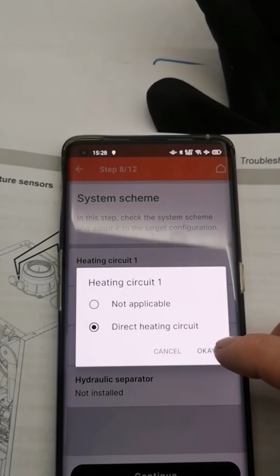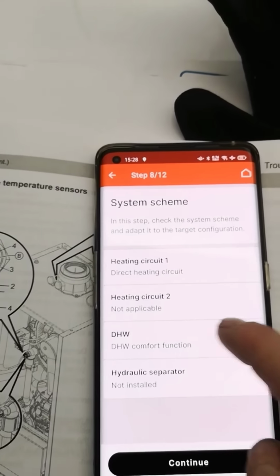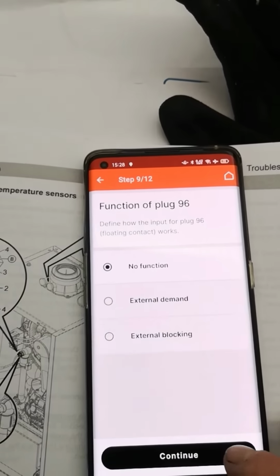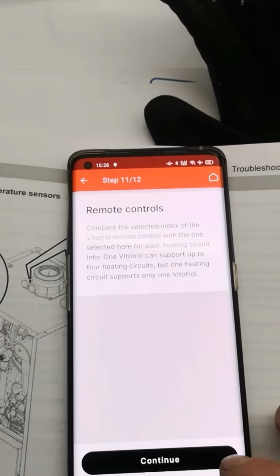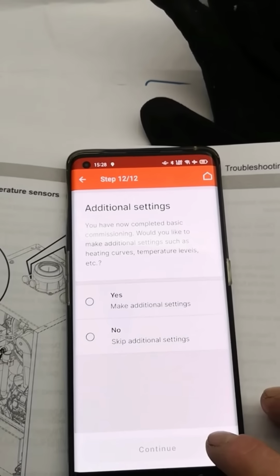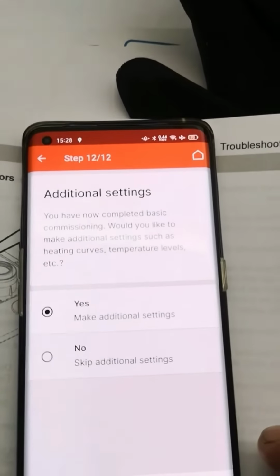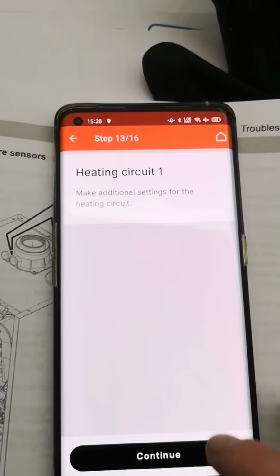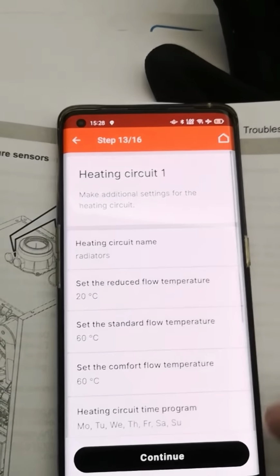So we can change various things within the menu. We can do additional settings as well. We can set the flow temperature, we can change the time programs. We can change the maximum speed of the pump depending on the size of the heating system. We can change the temperature of the hot water up and down.